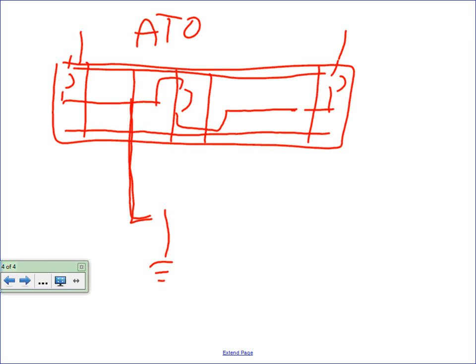So, say that was an 800 amp breaker. Well, now you've got 800 amps of neutral current that should be coming back on the neutral flowing to ground. And that's how a ground fault system works, because we read what's going on the phases and what's coming back on the neutral for that main. If it's 3,000 amps going out and only 2,200 amps coming back, we know we have 800 amps of ground fault current flowing in the system.